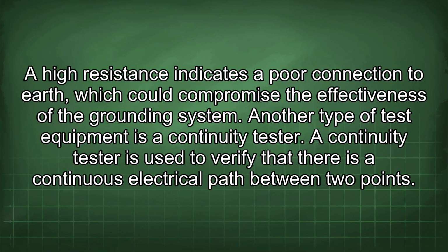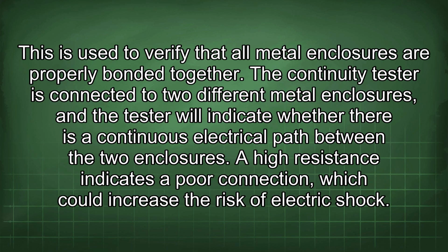Another type of test equipment is a continuity tester. A continuity tester is used to verify that there is a continuous electrical path between 2 points. This is used to verify that all metal enclosures are properly bonded together. The continuity tester is connected to 2 different metal enclosures, and the tester will indicate whether there is a continuous electrical path between the 2 enclosures. High resistance indicates a poor connection, which could increase the risk of electric shock.